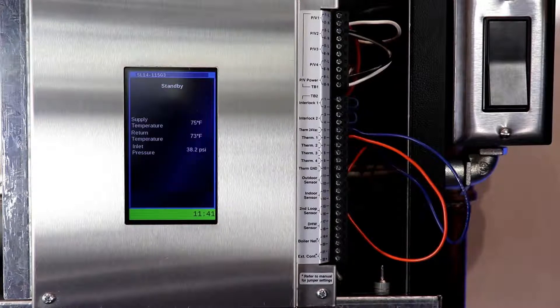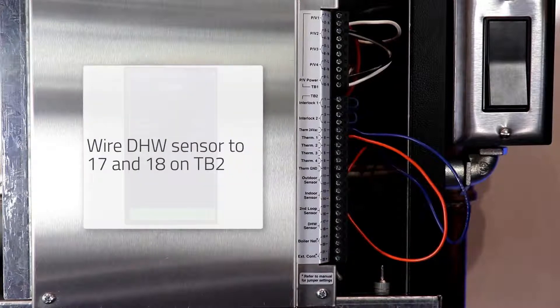If you are using a domestic hot water sensor, then the sensor will be wired into position 17 and 18 on the TB2 terminal. This is just for a 10K ohm type 2 thermistor for domestic hot water activation.